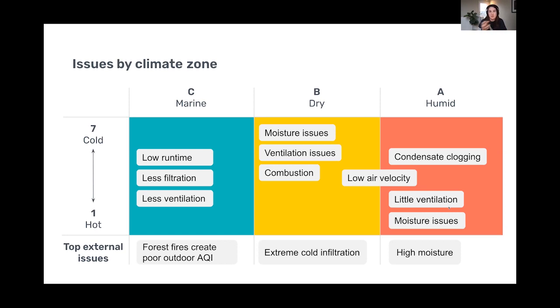Sometimes there are trust issues between homeowner and pro, so that's why we're trying to provide this centralized system where they can both have the transparency to instill the confidence that this is the right solution. But if we are in a humid climate and we're seeing high VOC levels, we can say, okay, because this is an existing customer, we know your home doesn't have as much ventilation as what we would recommend. So we are suggesting that you install a ventilating dehumidifier alongside an outdoor air damper to allow your home to be ventilated properly without the harm of introducing all this new humidity into the home.